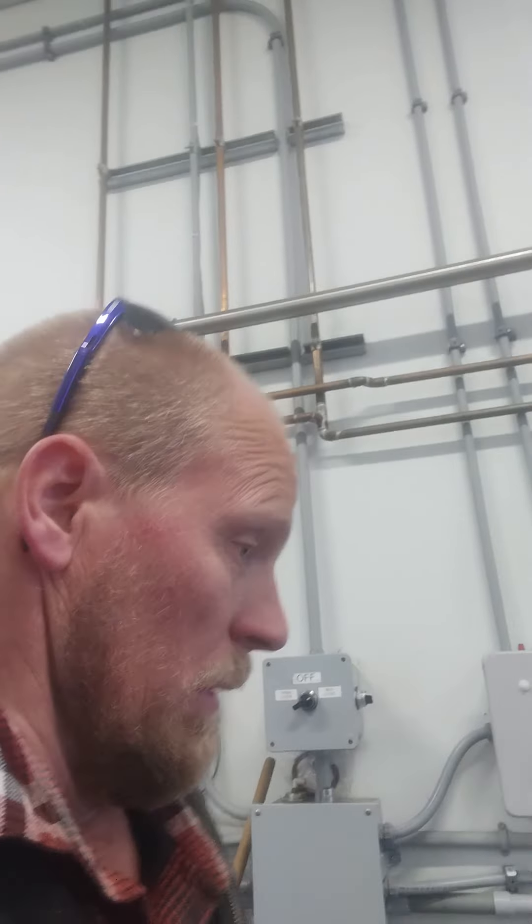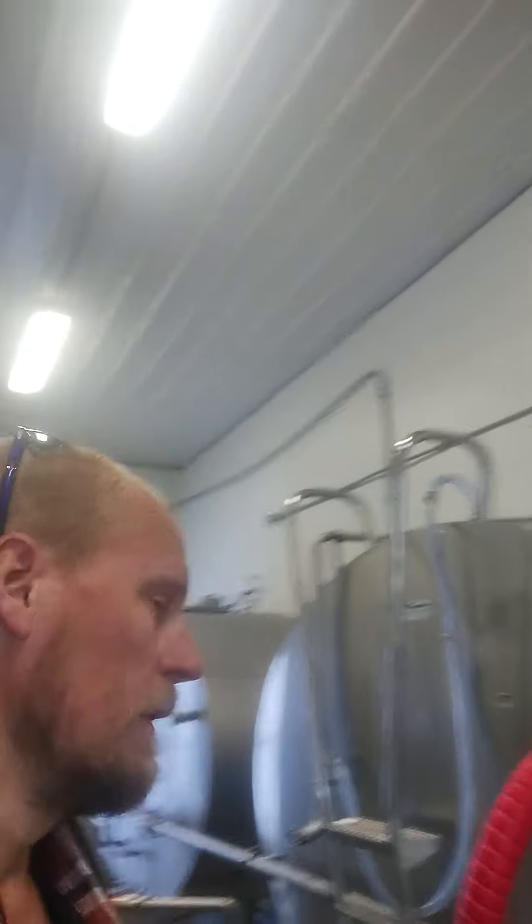So we make sure the tank is clean and ready. This tank will be filled with milk tonight. These tanks also have refrigeration on them — I just turned on this one when I started filling it, and it refrigerates the milk down to about 38 degrees. You can see this one right there is at 38 degrees, and this one I just turned on is at 43. That gives you an idea how cold the milk gets after it goes through the plate cooler.